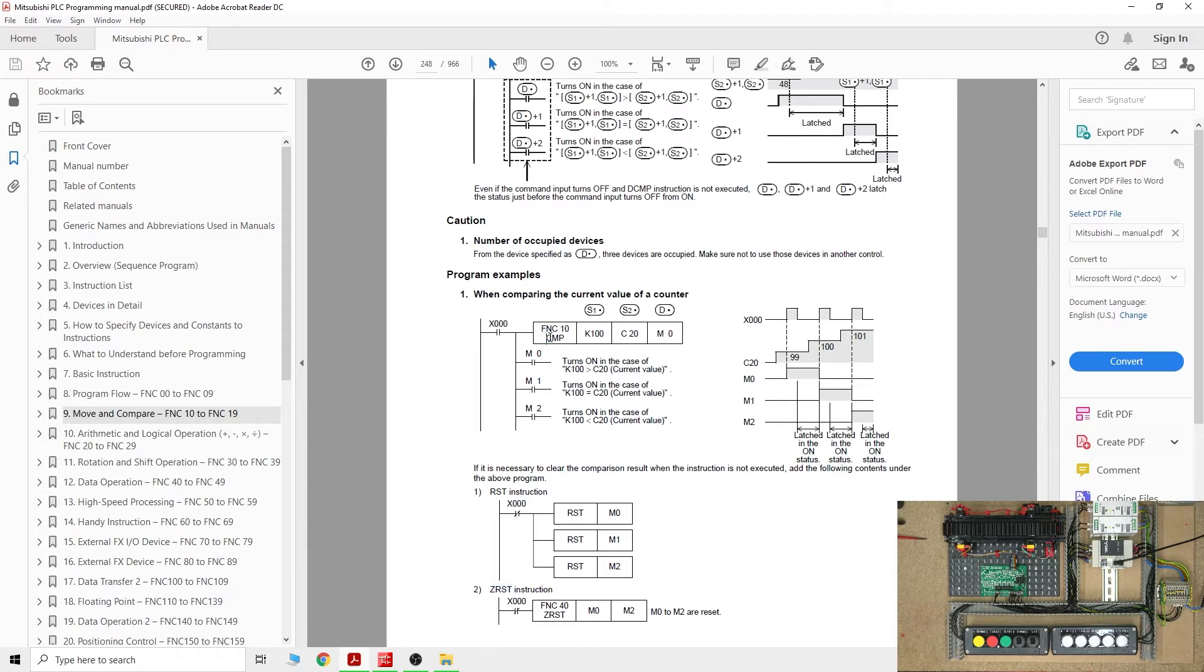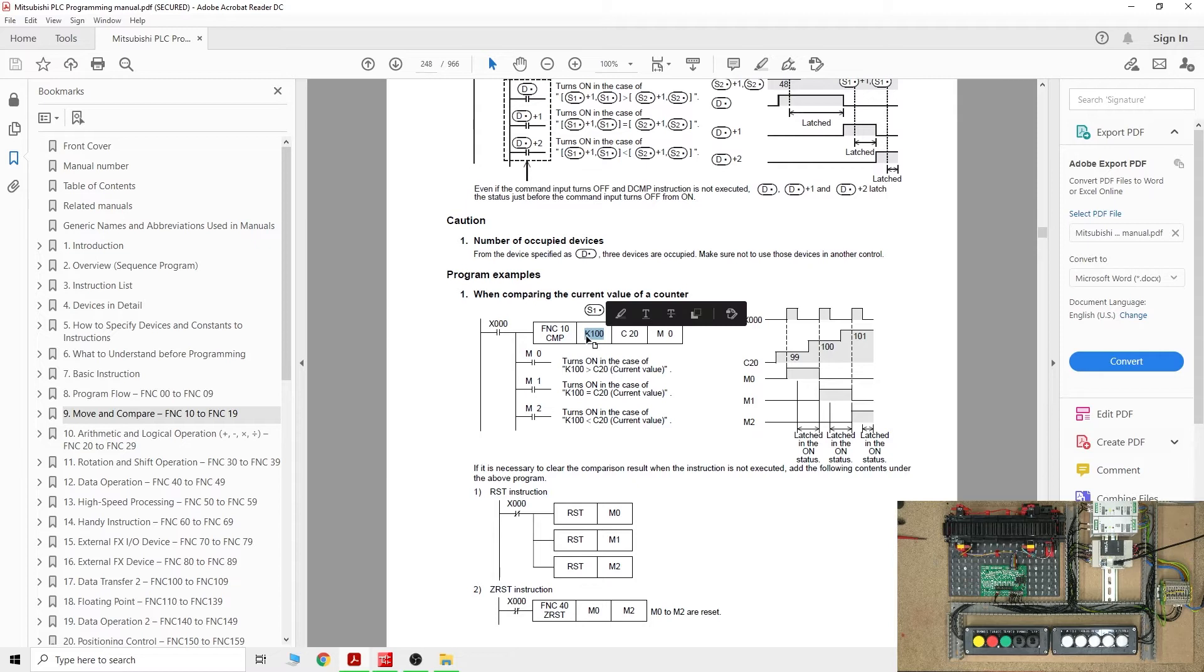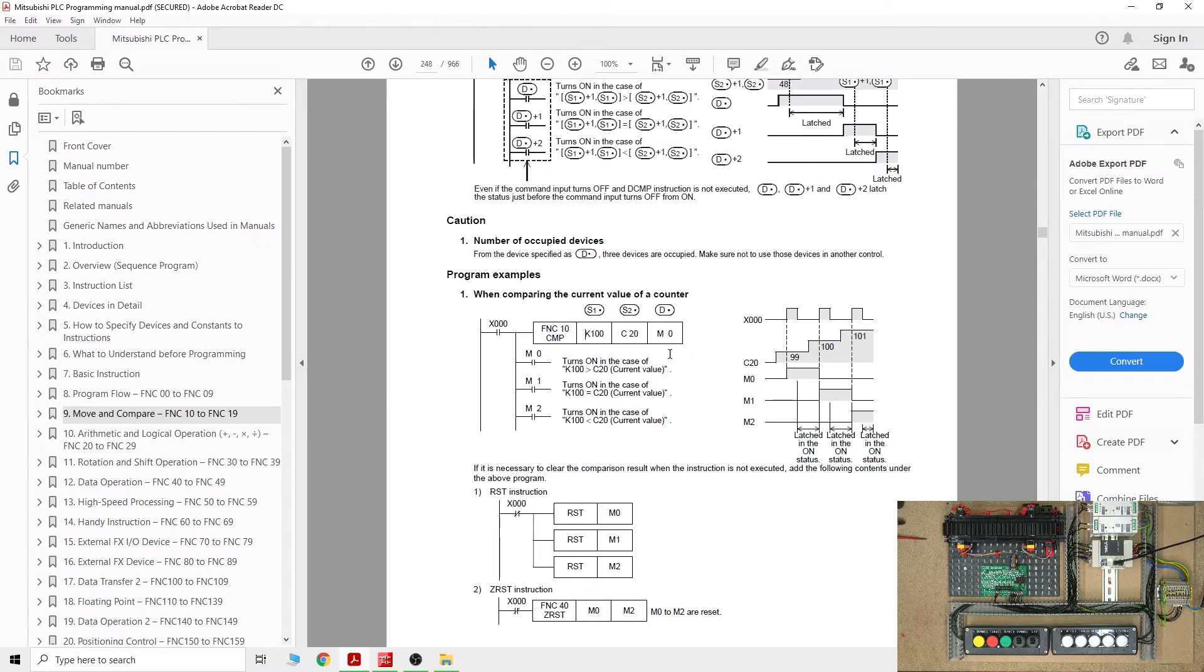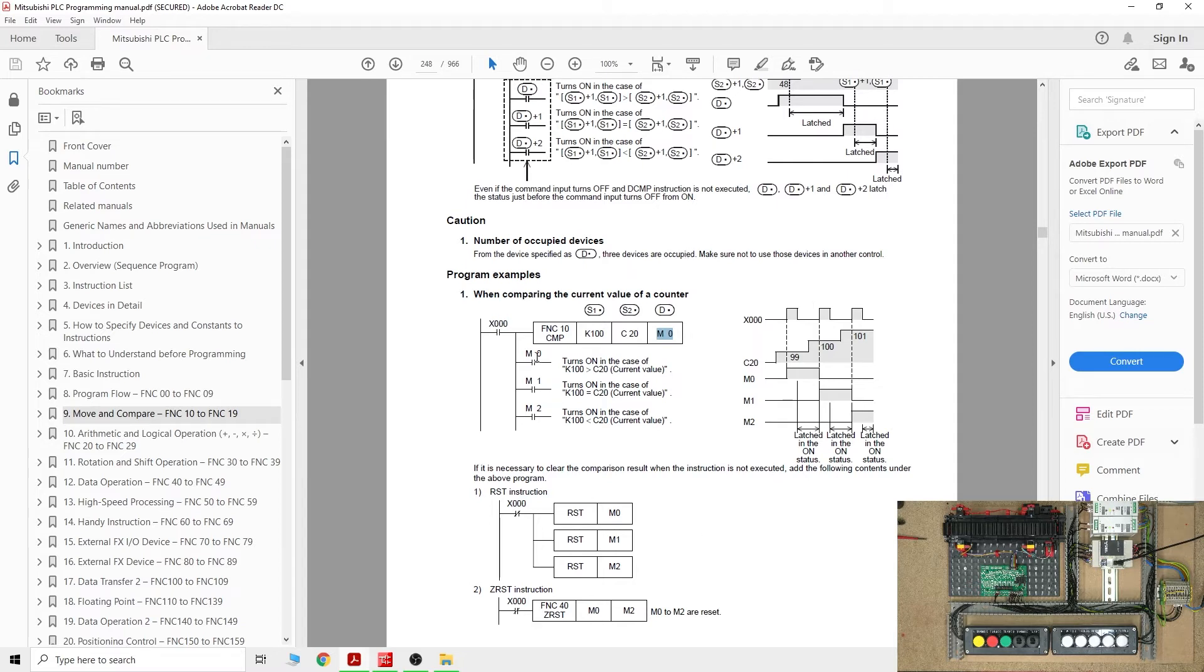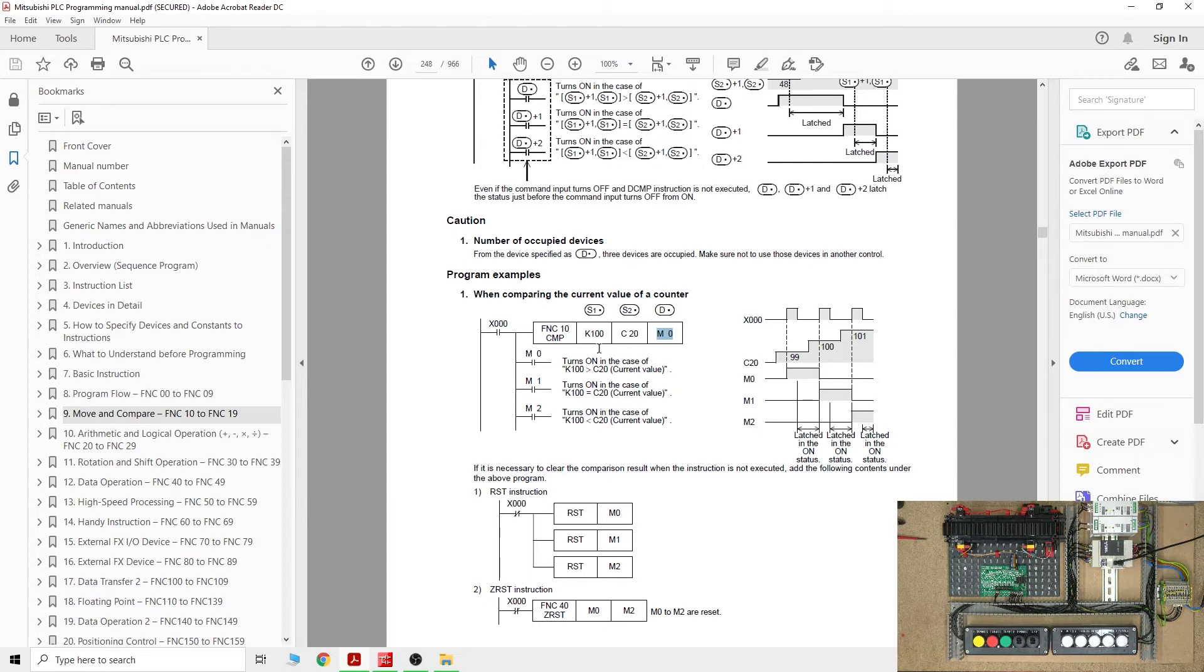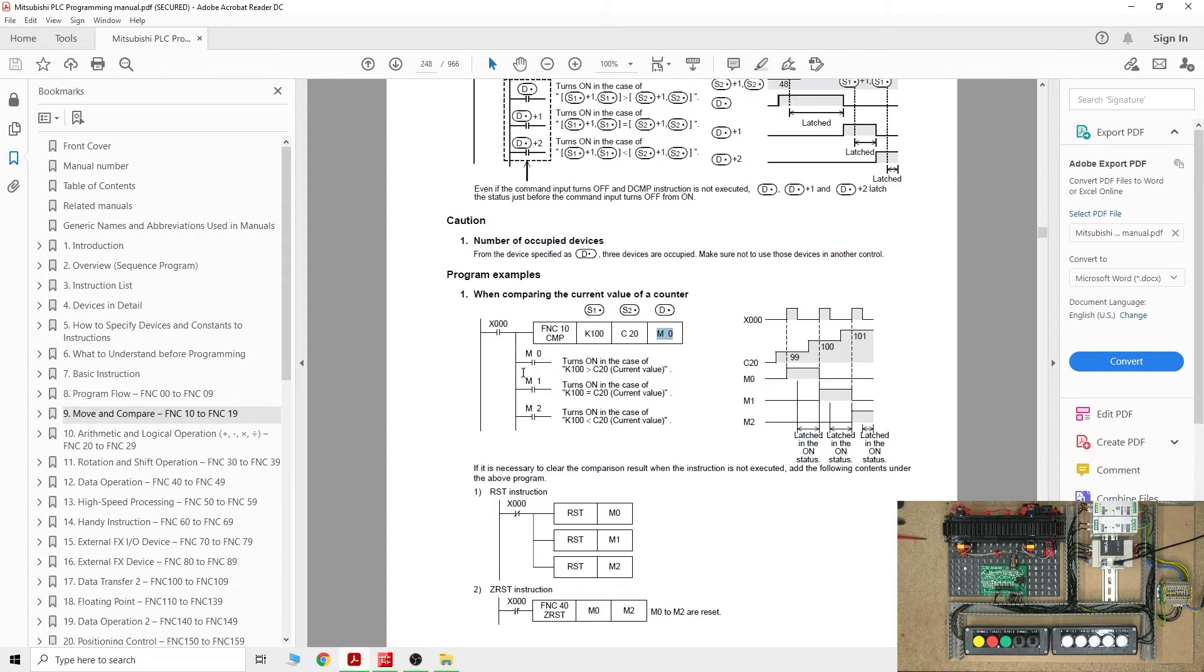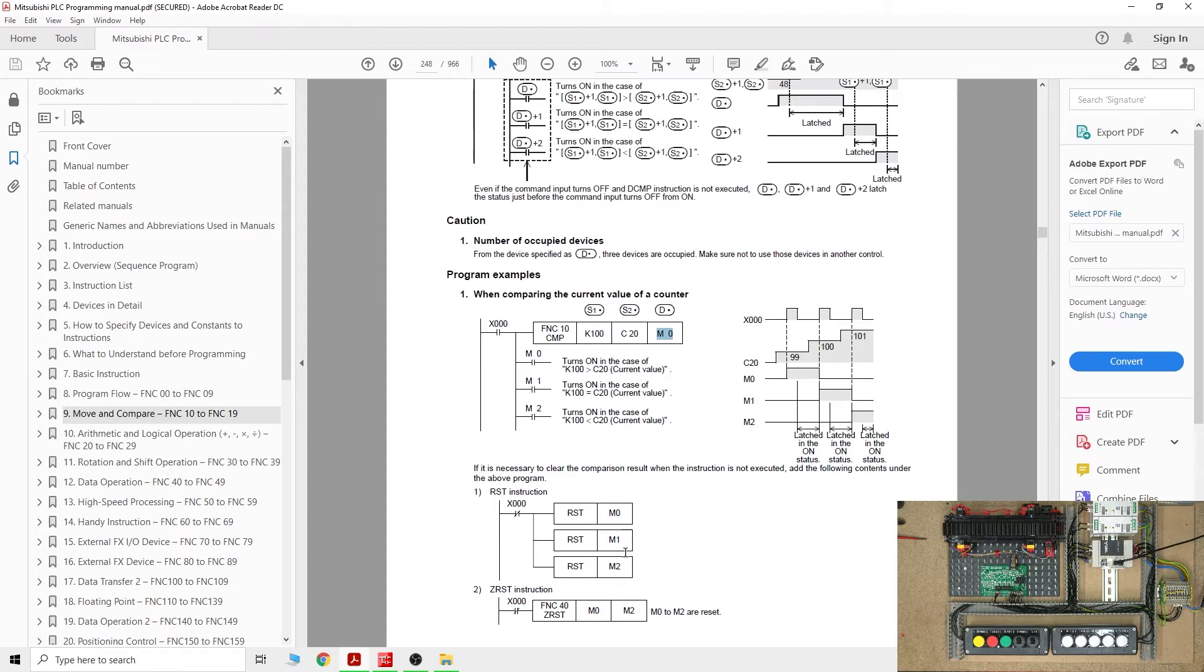If you see in here, what are we comparing? CMP is going to be a compare. Then the value, what value are we comparing? In this case, it says K100 and against what is the value in a counter and what bits you're going to be turning on once those values are reached. If you see in here, M0. Starting from M0, M1 and M2 is classed those three devices as are occupied. So you can see down there, M0, if K constant is higher than, then a value is higher than C20 value, it's going to turn on M0. If M1, if K100 is equal to value of C20, that will turn on M1. And if, obviously, from there on, if you want to turn on M2, you need to make sure the K value is below C20 value.